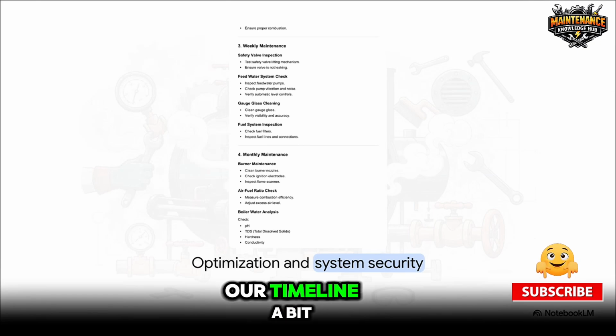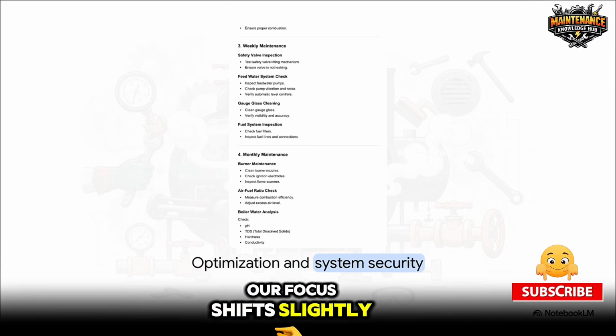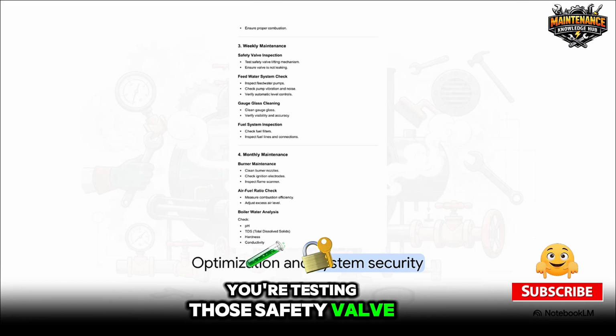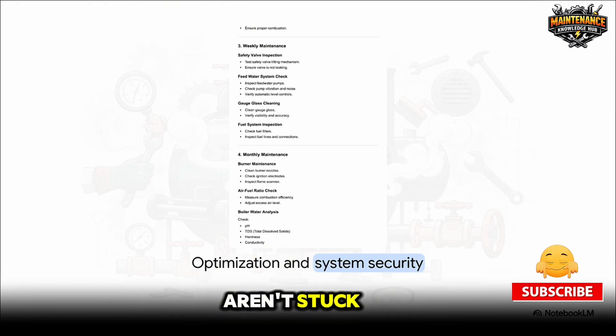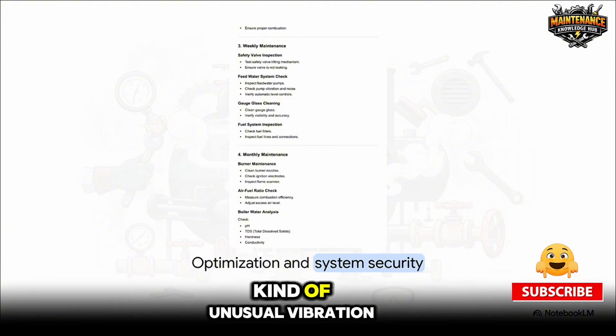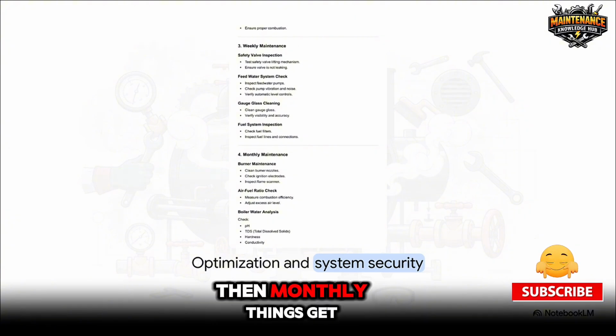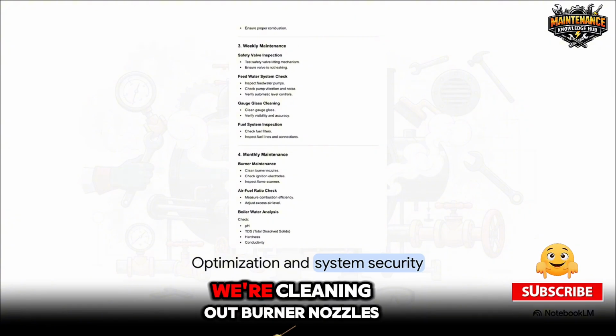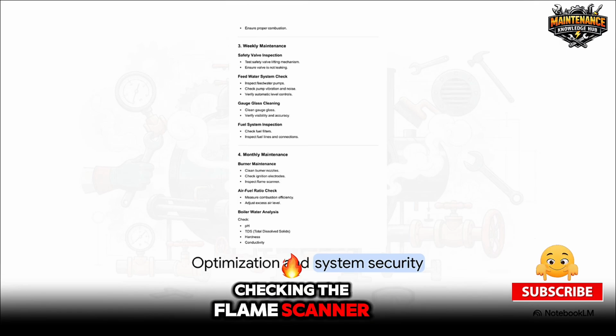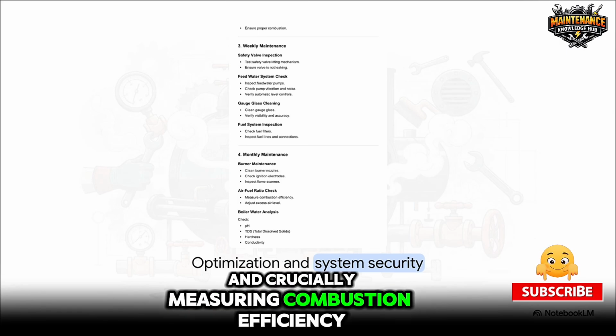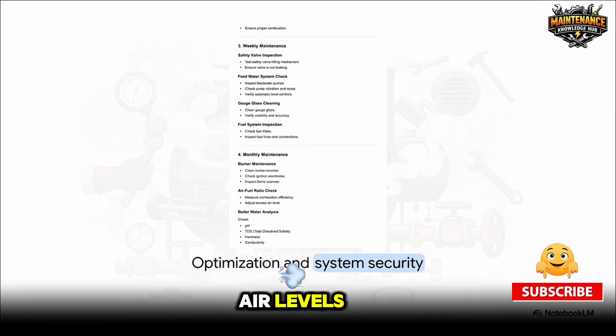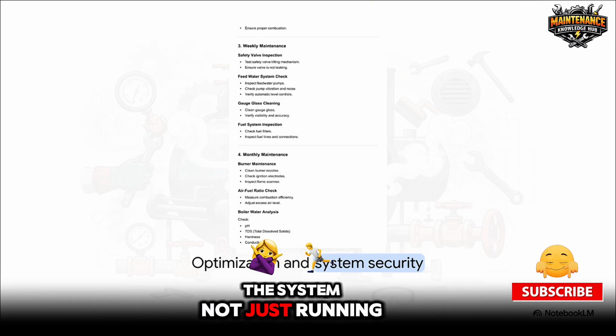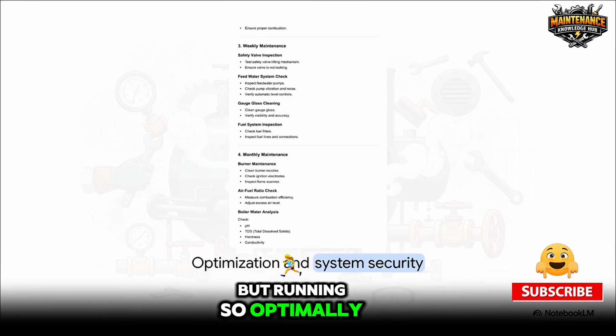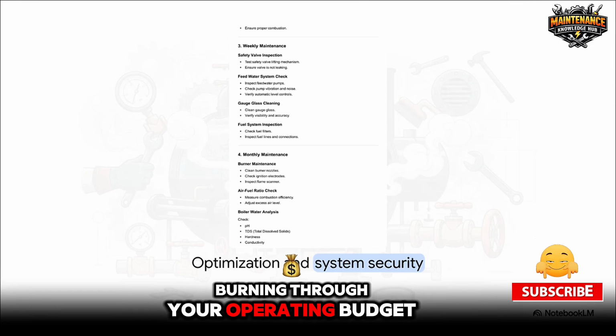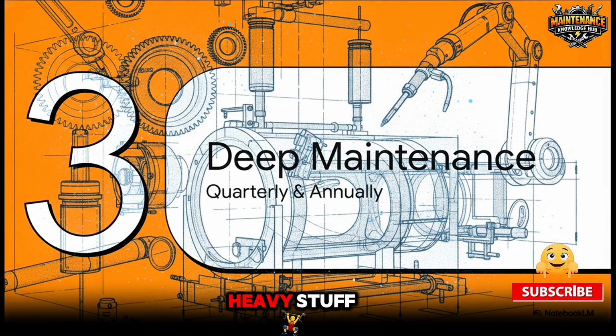As we scale up our timeline a bit, our focus shifts slightly toward optimization and system security. Weekly, you're testing those safety valve lifting mechanisms to ensure they aren't stuck, and you're checking your feed water pumps for any kind of unusual vibration. Then monthly, things get a bit more intensive. We're cleaning out burner nozzles, checking the flame scanner, and crucially, measuring combustion efficiency to adjust your excess air levels. It's all about keeping the system not just running, but running so optimally that you aren't quietly burning through your operating budget.